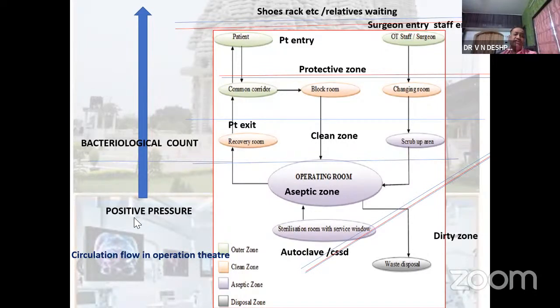If you look at the pressure gradients, the OT has to be positive pressure so that outside air doesn't enter, and the air flows from inside to out. The bacteriological count has to be low in the operating room, and it increasingly goes up as we move outside.